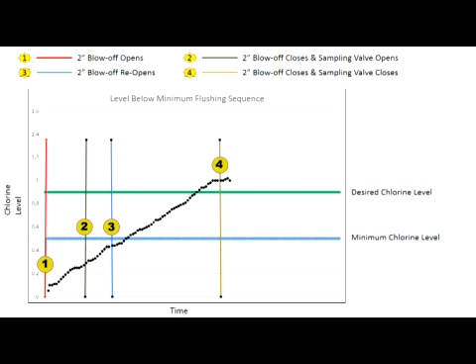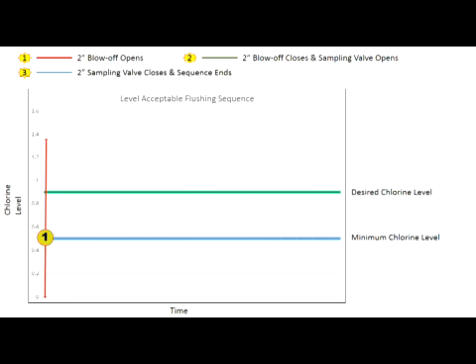Initial and final chlorine levels, time of day, and flush duration data is automatically recorded on the PLC and is available for download onto the microSD card. If the sampled water's residual level is above the program minimum chlorine level, the unit will continue to sample and check to make sure the residual doesn't drop below the minimum residual level for the sample duration time. As long as the residual level remains above the minimum level, no additional flushing occurs.